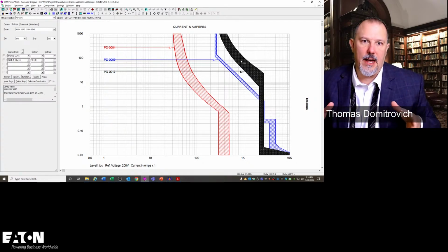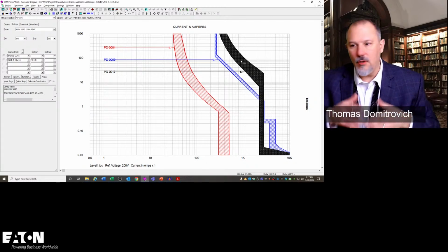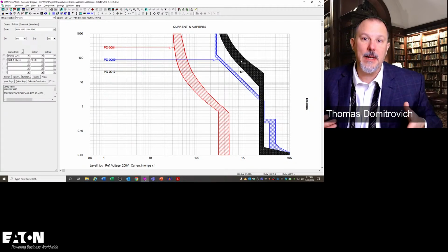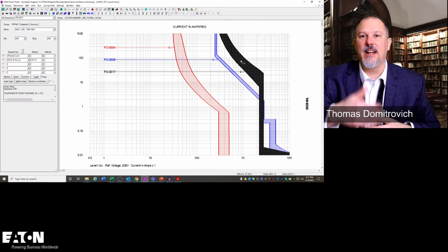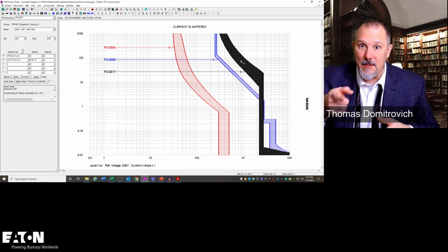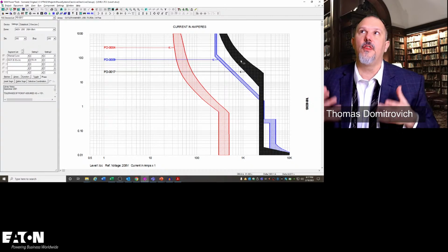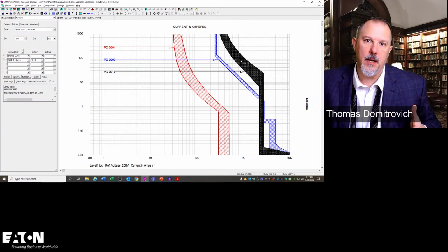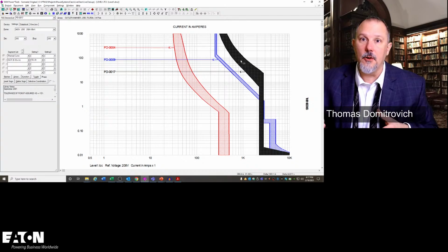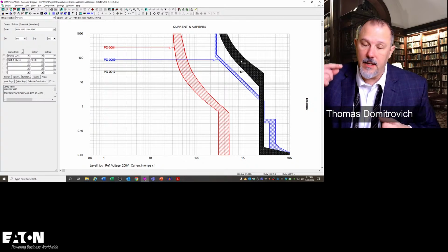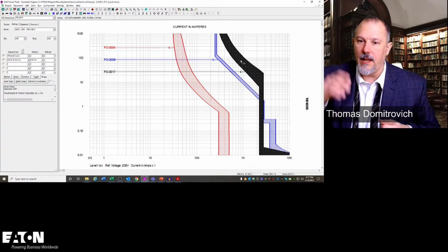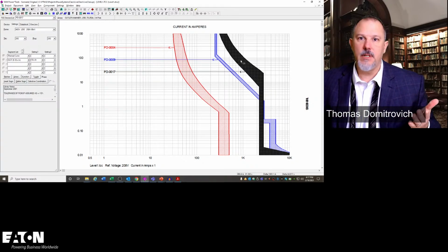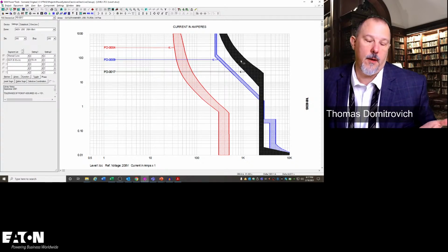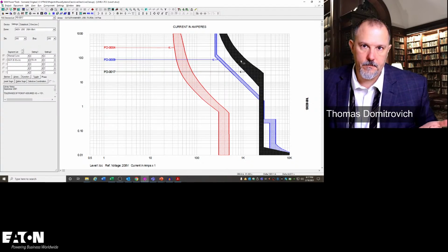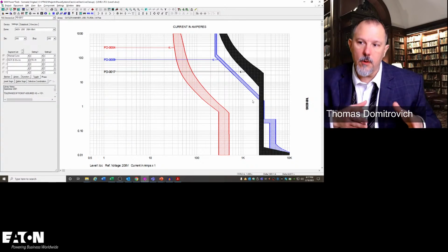So you look at that and you say, you can't plan for the unexpected, but when the unexpected happens, that's when our design principles go into place to say, look, I thought about that. Yeah, it rarely occurs, but when it does, thank God you had that backup and you did the engineering up front. He did all the maintenance on his part. That transfer switch transferred, that generator started, and it worked like clockwork. It met the time limits that they expected, but they didn't coordinate, and it took out the generator. So there they were, trying to figure out what the heck happened. So coordination is important.